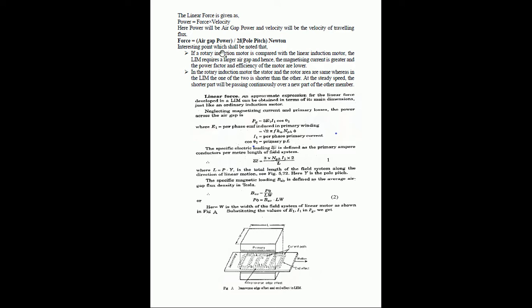An interesting point to be noted: if a rotary induction motor is compared with the linear induction motor, the linear induction motor requires a larger air gap, and hence the magnetizing current is greater and the power factor and efficiency of the motor are lower. In the rotary induction motor, the stator and the rotor areas are the same, whereas in the linear induction motor, one of the two is shorter than the other. At a steady speed, the shorter part will be passing continuously over a new part of the longer one.